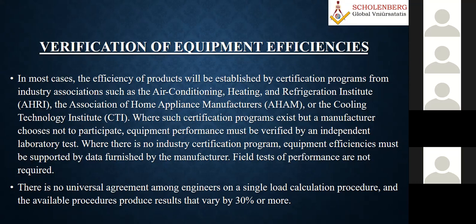Like last time when I was talking about hospital accreditation, somebody was asking what the things are. Yes, so if you go for the checklist, one of the checklist items is, are you following this type of standards? For that, there will be weightages. So the verification of the equipment efficiency is very important. And more than that, there may be the certificate, but I strongly recommend what I told in the first class. Suppose you are trying to take a higher capacity, very special, very critical equipment, you should always go to the manufacturing plant and do the performance test at the manufacturing place itself. Then you verify and issue the test certificate. And after coming back, when you are installing, at that time also we can verify it.